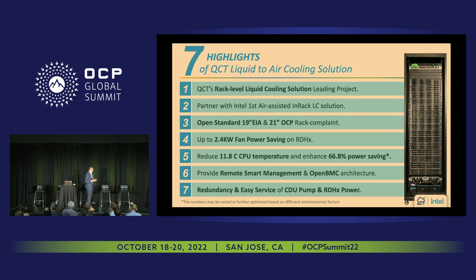We certainly partner, one of our key partners is with Intel, on the first air-assisted in-rack liquid cooling solution. For the purposes of this event today, we also provide open standards on both 19 and 21-inch OCP rack mount compliance. We do the 2.4 kilowatt fan power saving, and on the overall average, to give you guys an idea, by having this system in place, it reduces about 11.8 Celsius.